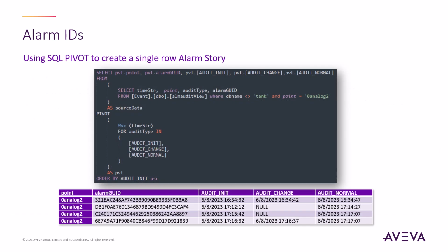With these two columns, integrators can now more easily maintain the landing table code that they need to interface with the third-party alarm analytics software. It is anticipated that different landing tables could be developed for the different types of alarm metrics being measured. The group by clause is used on the GUID column to bring all of the events for a single alarm together, and the event type column is used to pivot the timestamp column into the appropriate column in the landing table.